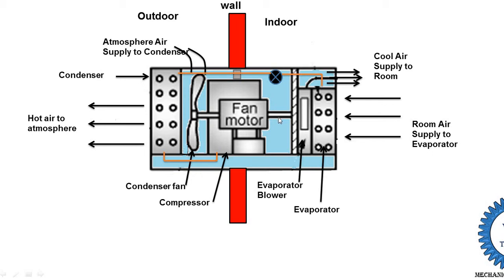The window air conditioning system is used for cooling smaller rooms and reducing temperature. The process performed is cooling and dehumidification — room air supplied to the evaporator undergoes both processes. The system controls air temperature, humidity, velocity, and cleanliness. A filter at the front of the evaporator removes dust particles, and a tray below the evaporator collects water droplets condensed from the room air's humidity, which are then drained outside the system.